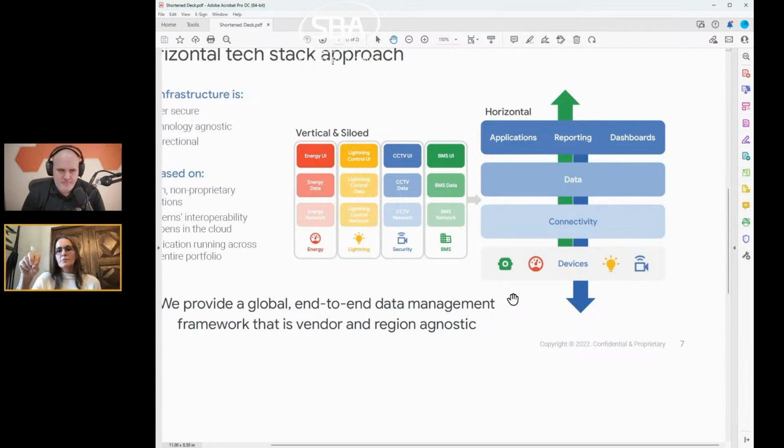And then we have a master systems integrator who's trained on our digital building ontology. So at Google, we created our own ontology. We're not using Brick or Haystack, but similarly, we have a tagging ontology. We created our own because at the time when we started a few years back, the existing ontologies were not giving the relationships or serving the needs that we had.